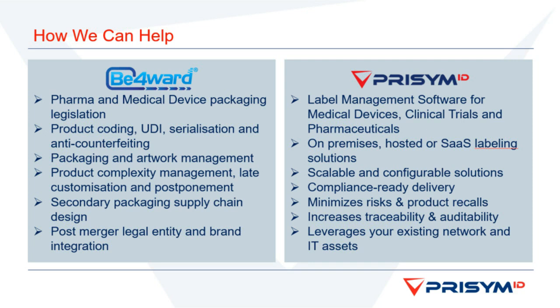And as well, the EU MDR UDI and the FDA UDI allow you to also include additional data as part of that barcode, which you need to be careful of because it does push you to include the UDI components at the start of that data, and then any additional piece of data you want to include at the end, which somewhat goes against some of the GS1 guidelines that you should include all your fixed length AIs first within that barcode, but the UDI is pushing you to include your UDI data, so things like your lot number would need to come earlier in that data.